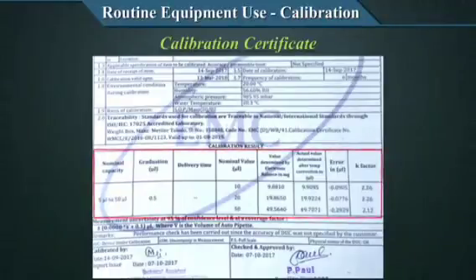Calibration results obtained and units of measurement, including a record of the readings obtained during calibration for each of the calibration values, and record of the calculation of the accuracy and precision of all sets of values, any use limitations of the equipment calibrated, any correction factor, the uncertainty of measurement of results.